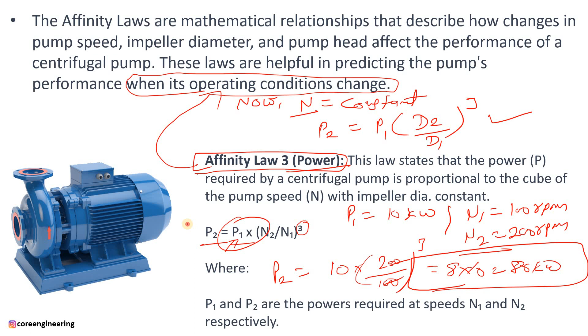Sometimes what happens is that we simply place the order for an oversized pump. That is not our requirement. So what we could do is simply trim the impeller diameter, or we could use a VFD. How can we trim the impeller diameter? We can only trim the impeller diameter when we know how to use the affinity law. By using the affinity law, you can predict the pump performance when you change its operating condition. After changing the operating condition, you can simply put those values in your affinity law formula and find out the new pump performance. Are you getting my point what I want to say? So this is very helpful when we select a centrifugal pump.